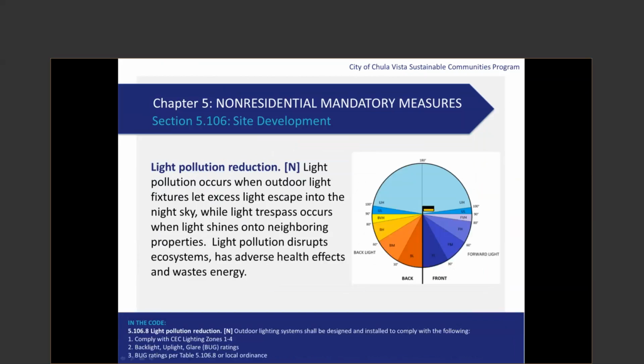Light pollution is addressed in CalGreen with limits on the amount of light that can escape an outdoor lighting fixture. We want to maximize the light in the intended area, the downlight, shown in dark purple, while minimizing light that escapes in three other directions: behind the fixture in the orange areas, called backlight; upward, shown in light blue, called uplight; or directly into people's eyes in the light purple zones, called glare. There's a standardized rating for backlight, uplight, and glare describing the amount of light emitted in those directions, referred to by the acronym BUG ratings, and CalGreen sets limits as to what is allowed.